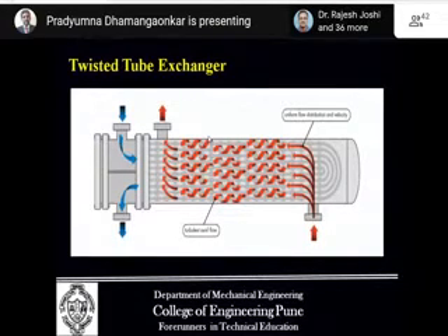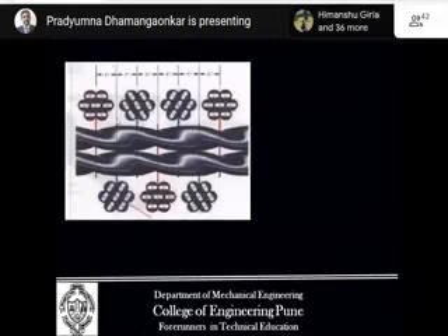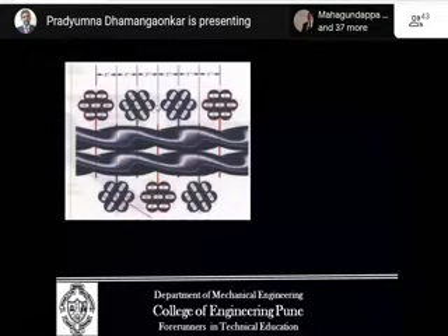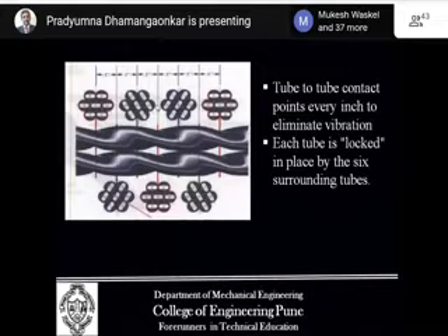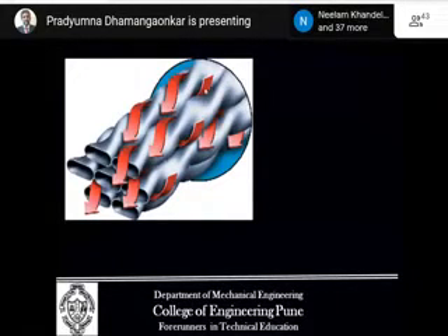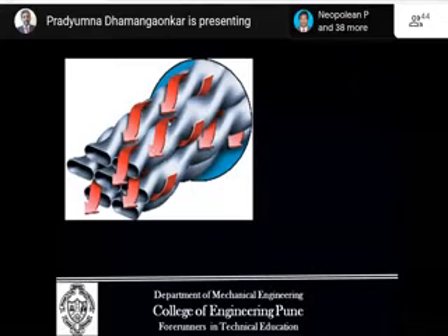This is a twisted tube heat exchanger. As is seen, the tubes are twisted and assembled in such a way that, as shown in this figure, there is a point of contact after each 1 inch. The tubes are placed in such a way that one tube is fixed or surrounded by 6 surrounding tubes. The better part is that the flow induced vibration is reduced. Contact points every inch eliminate vibration, and each tube is locked in place by surrounding tubes. This is how the shell side flow pattern is established. There is less restriction, less pressure drop and a higher heat transfer coefficient, and thus a higher heat transfer rate.